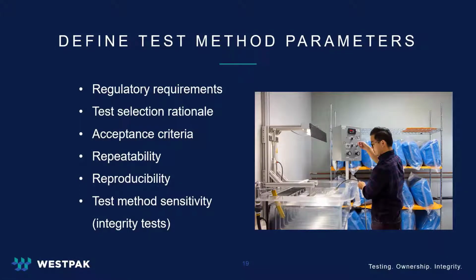The acceptance criteria for test method validations will be dependent on if the test method is qualitative or quantitative. For qualitative tests like gross leak testing, the data that is generated will be an observation based on defined characteristics like a breach in the sterile barrier. The acceptance criteria for quantitative tests, like seal strength testing on the other hand, will produce a data set that must fall within a defined range. If the operator is able to identify known defects for a qualitative test or produce a data set that falls within the acceptance criteria for quantitative tests, this will then provide evidence that the test method is repeatable and reproducible.